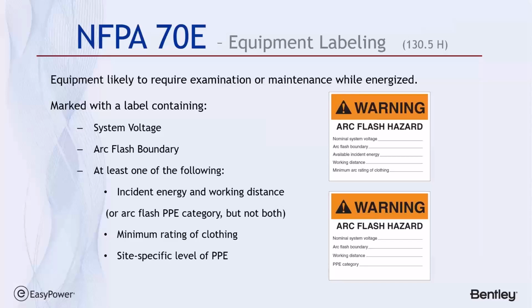And to that point, each piece of equipment needs to have a warning label that includes the system voltage, the arc flash boundary, and at least one of the following: the incident energy and working distance, or the arc flash category, but not both, and the minimum rating of clothing or site-specific PPE.